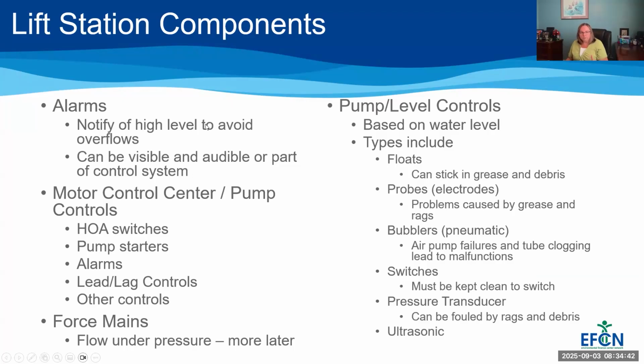The alarms can be visible, they can be audible, meaning it might be a flashing light, it might be a siren sound, it might be some type of buzzing, or it can be part of your control system if you have SCADA, and you can get a notification at your control center that there's an alarm happening, or you can have all of the above for alarms.